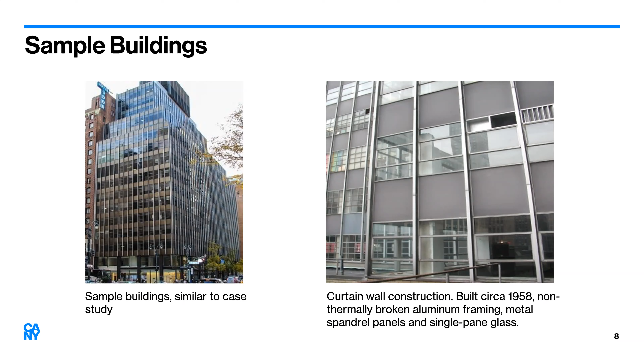The problem is that glass is all single pane. The metal panel you see is probably an eighth-inch thick piece of aluminum, with zero insulation. We'll show you some photos of what's behind that shortly. Those vertical mullions are extruded aluminum, and that's the structure of the wall, but it's also all outside, so that's acting as a gigantic thermal conductor. You're losing a lot of energy right there. You have all that mass on the outside generating heat loss, with no thermal break from interior to exterior. There's nothing to stop that conduction of hot and cold from interior to exterior and vice versa.